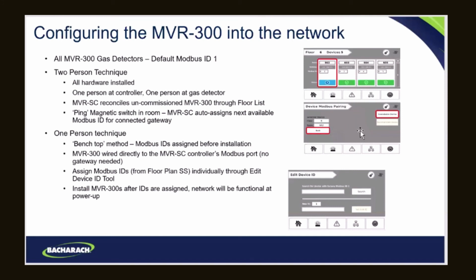There's going to be another screen that comes up that lists the floor, the room, and if all of that lines up with your Modbus ID, the only thing that needs to happen is the person in the room will use a magnetic wand to ping the MVR 300 in the room, and the controller will recognize that, and the person at the controller will do the commission device, and it will all be done for you. So each one of those devices, and then that person in the room goes to the next one on the list, and the same thing is done at the controller.